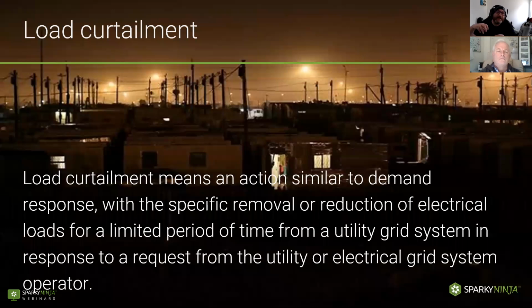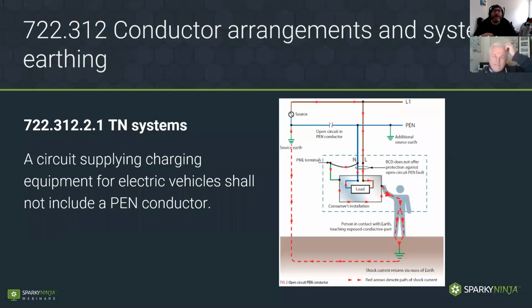Okay, so going into the area of protection. Now, the area of protection has been one that's been chewed on and worked on a lot over the past few years, and that's because of this issue of the PEN conductor. So TN systems. We're not yet in the protective section. We're in 722.312, which is the conductor arrangements, but it just says there that a circuit supplying charging equipment for electric vehicles will not include a PEN conductor.